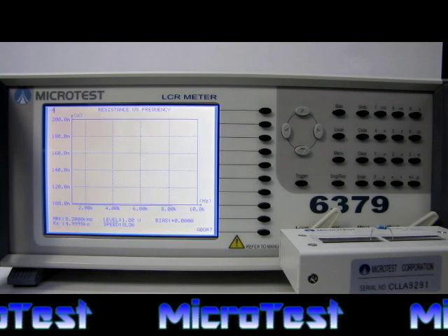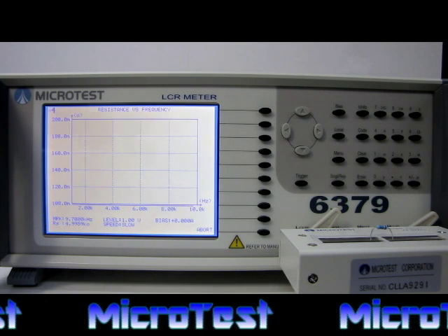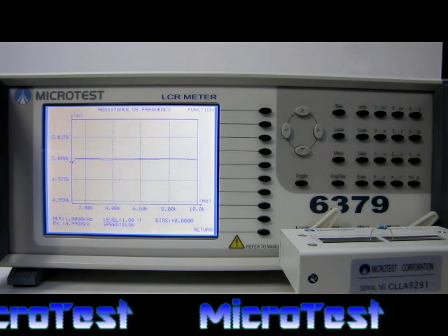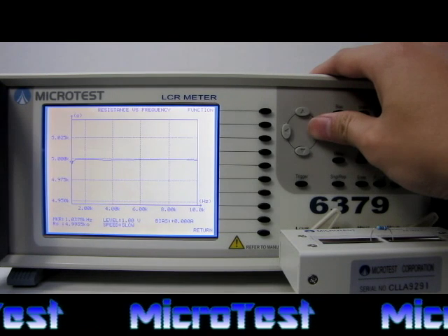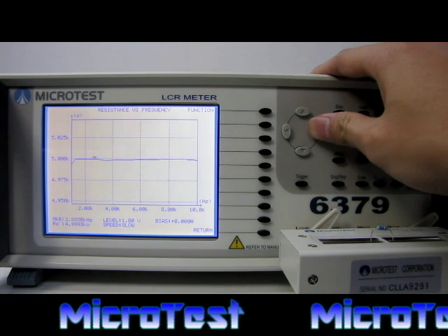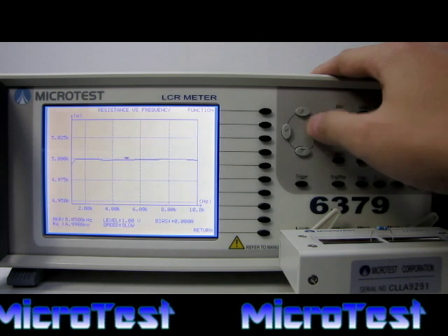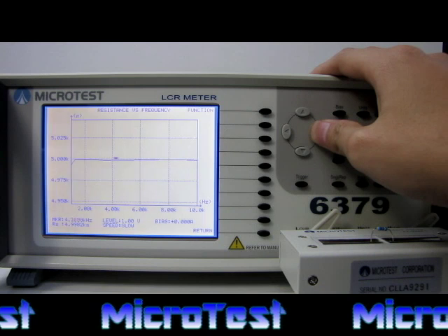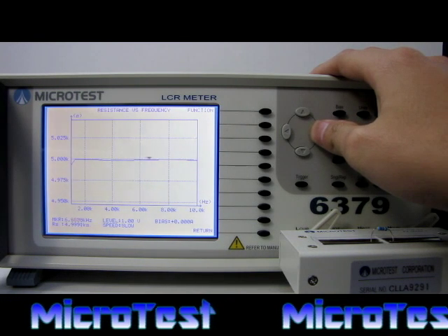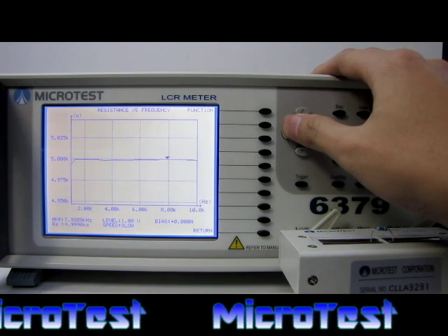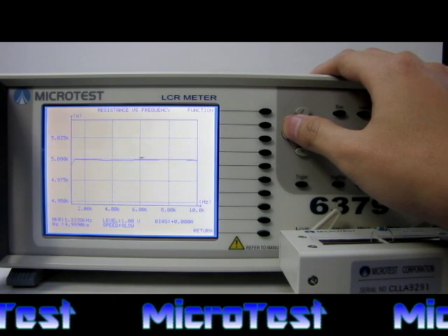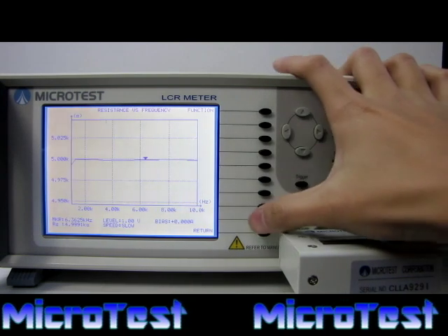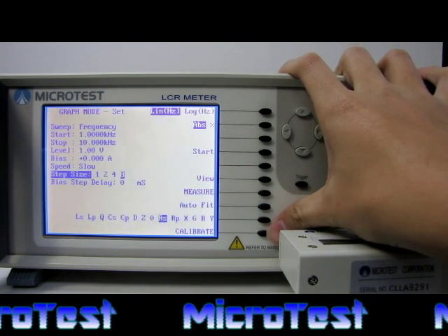While sweep is being performed, the bottom left will display the frequency being scanned as well as the result. Once sweep is completed, the graph will be displayed in full. Use the arrow keys to select specific points in which to further analyze. To change any settings, press S10 Return to return to previous screen.